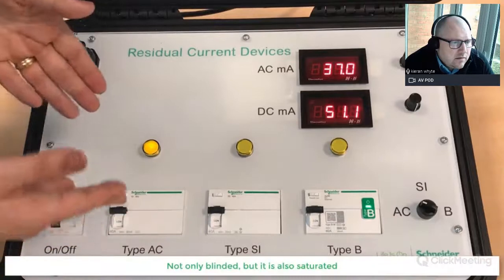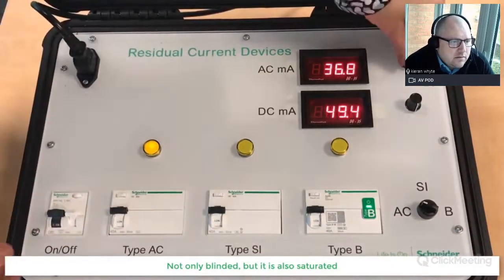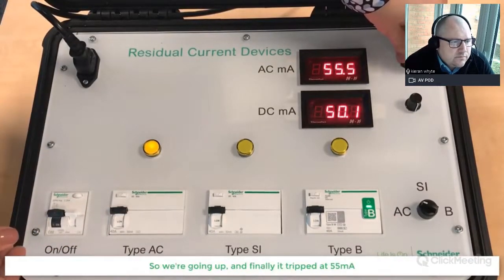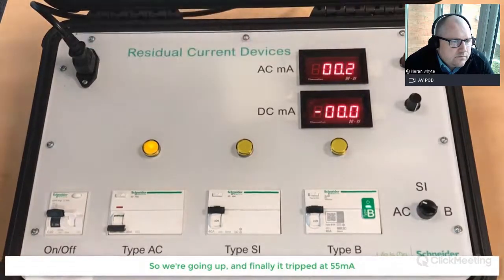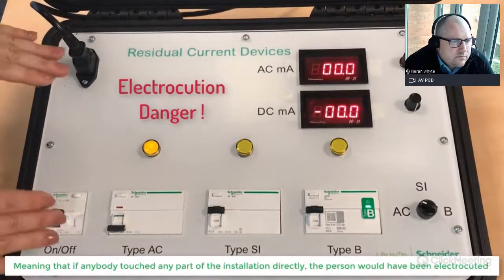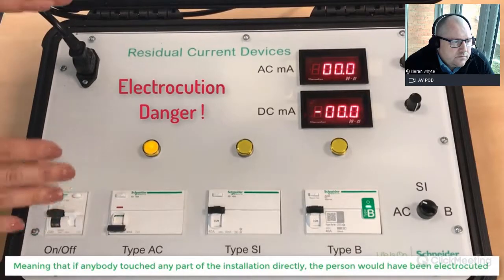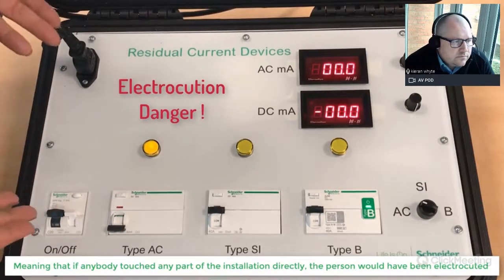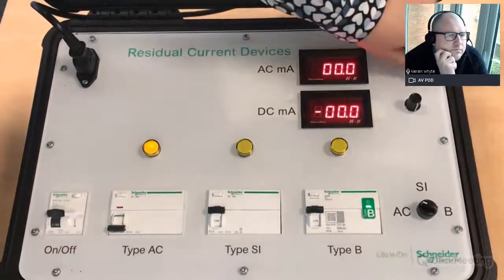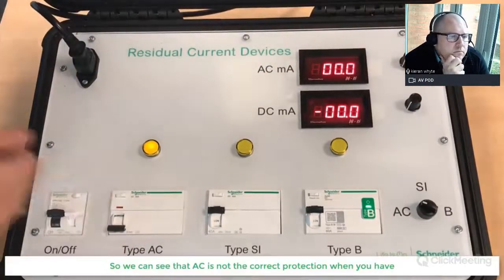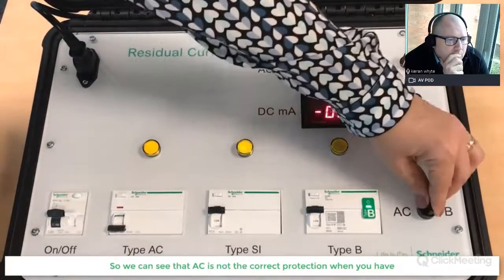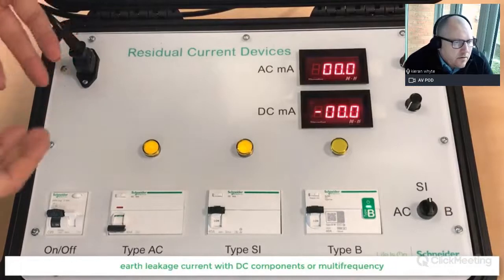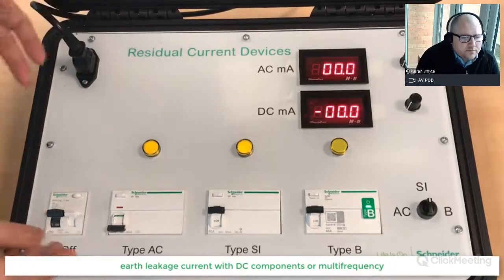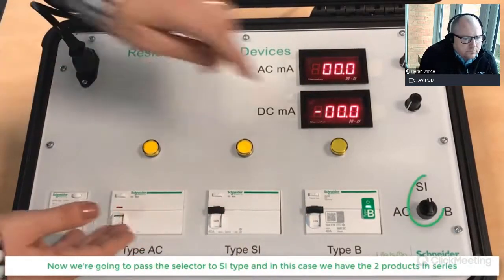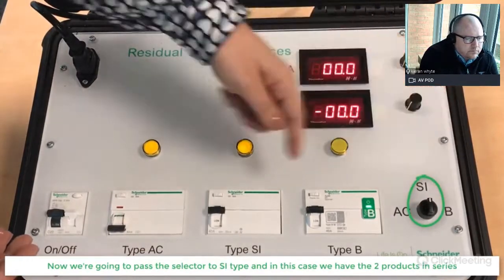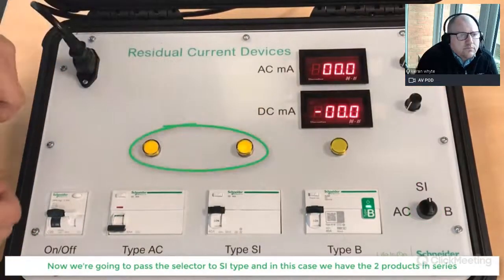Not only blind, but it's also saturated. So we're going up, and finally it tripped at 55, meaning that if anybody touched any part of the installation directly, they would get electrocuted. So what we can see is that AC is not the correct protection when you have earth leakage current with DC components or multi-frequencies. Now what we're going to do is to test, pass the selector to SI type, and in this case we have these two products in series.